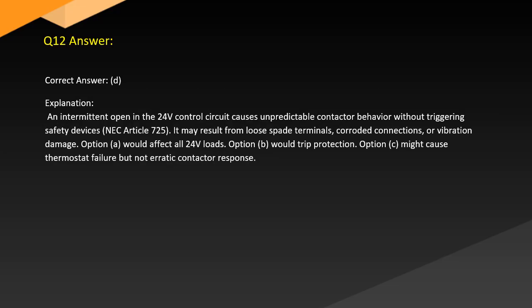Answer. Correct answer: D. Explanation. An intermittent open in the 24V control circuit causes unpredictable contactor behavior without triggering safety devices. NEC Article 725. It may result from loose spade terminals, corroded connections, or vibration damage. Option A would affect all 24V loads. Option B would trip protection. Option C might cause thermostat failure but not erratic contactor response.